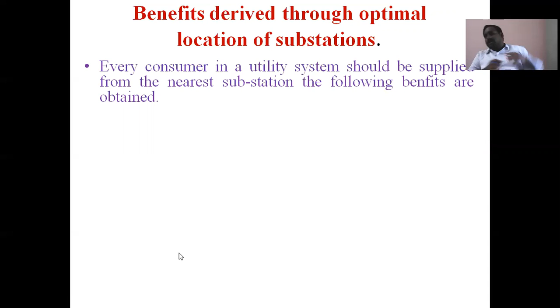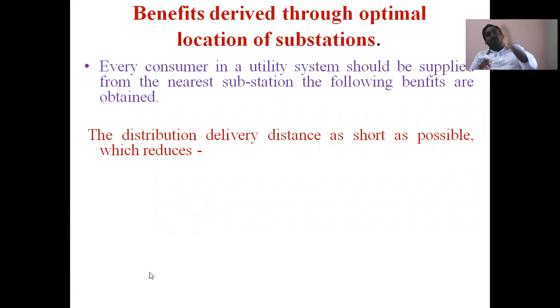The next concept is the benefits derived through optimal location of a substation. When we find the optimal location of a substation, what are the benefits derived? For example, such an optimal location is nearer to the consumer, so the distance between the consumer and the substation is reduced. What are the advantages? Failure cost reduces, electrical power losses reduce, power loss costs are also reduced, and service interruption exposure also reduces. Hence, a substation must be located as close as possible to the consumer. These are the benefits due to the optimal location of a substation.